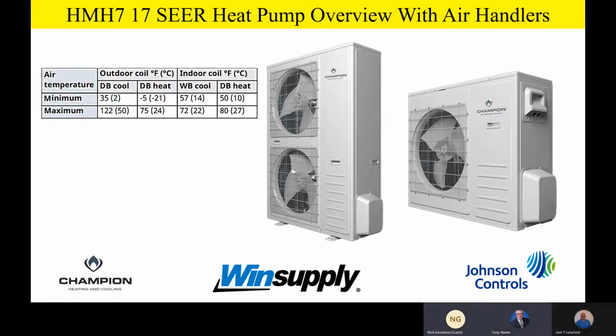Everybody good? I think that maximum of 122 is important. I think so. Certainly you'll have applications in the deep south where you're gonna hit that. So I think that's a real good feature for the unit. Absolutely. And the only place that we start getting into a little bit of trouble with that is way out in the desert Southwest, Arizona, New Mexico, southern Nevada, where they see 125, 130 degree ambient temperatures, and then high altitude on top of that, so the air is really thin, trying to pull that thin air across those fans outside, and real high temperature, like I said. So the only place we've had any issues at all, or any not degrading but derating issues, have been in the desert Southwest, as I mentioned, where we have those really high desert temperatures and altitudes that we have to contend with. Good.